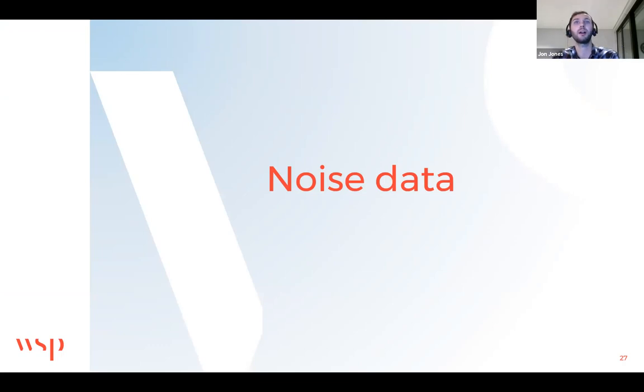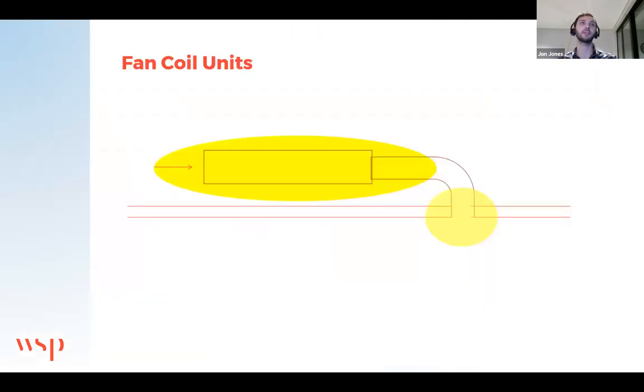So a little bit on noise data here. This ties in with a common thing that we have to deal with, and it's sort of good and bad data essentially. Taking a fan coil unit as an example, there are two main noise sources that we'd look to consider. One would be a combination of the inlet and casing radiated noise, and one, very separately, would be the supply point at the end of the ductwork, wherever it's supplying the room.